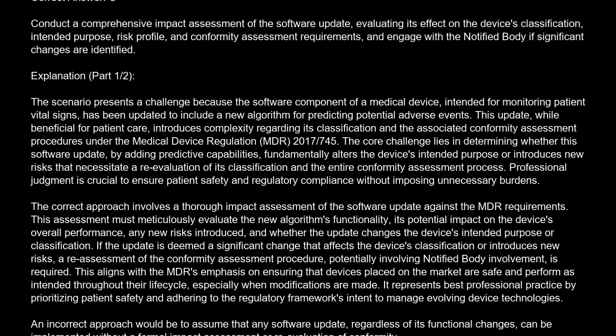The correct answer is C. Conduct a comprehensive impact assessment of the software update, evaluating its effect on the device's classification, intended purpose, risk profile, and conformity assessment requirements, and engage with the notified body if significant changes are identified. Explanation. The scenario presents a challenge because the software component of a medical device, intended for monitoring patient vital signs, has been updated to include a new algorithm for predicting potential adverse events.